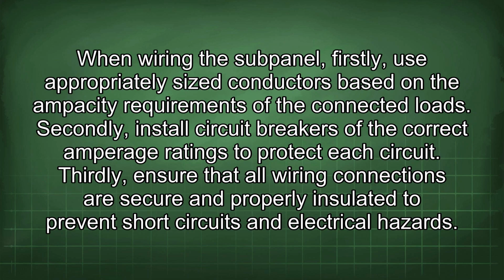When wiring the subpanel, firstly, use appropriately sized conductors based on the ampacity requirements of the connected loads. Secondly, install circuit breakers of the correct amperage ratings to protect each circuit. Thirdly, ensure that all wiring connections are secure and properly insulated to prevent short circuits and electrical hazards.